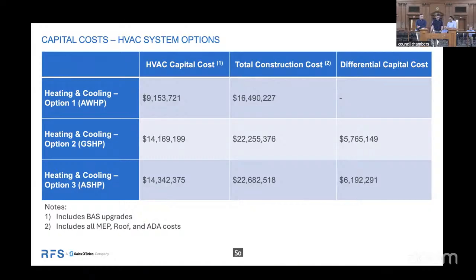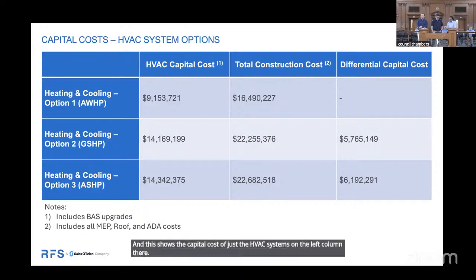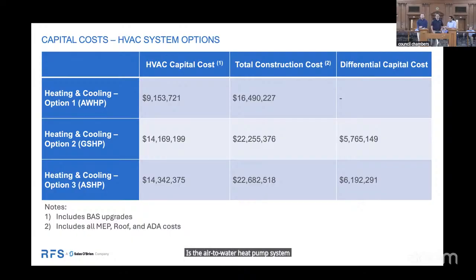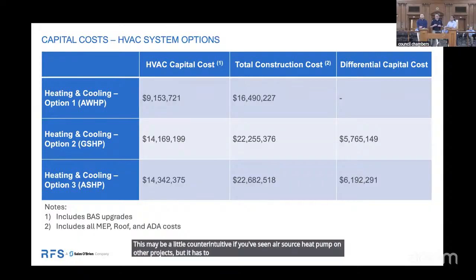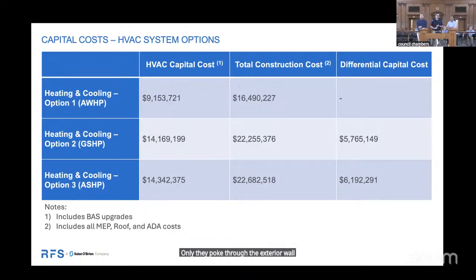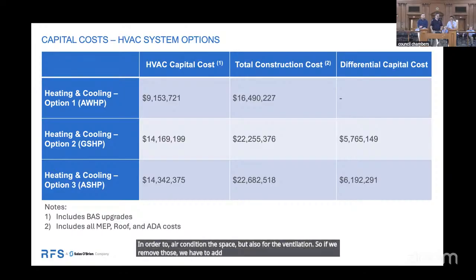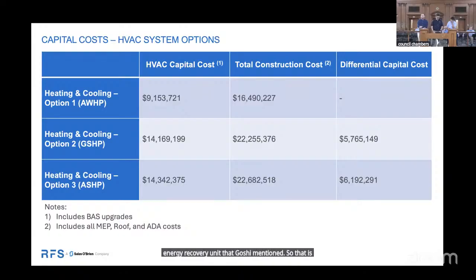This shows the capital cost of just the HVAC systems in the left column. You can see the cheapest capital cost is the air-to-water heat pump system. This may be a little counterintuitive if you've seen air source heat pump on other projects, but it has to do with the nuances of this project, specifically that we are removing the unit ventilators. The unit ventilators, as Goshi mentioned, not only poke through the exterior wall to air condition the space, but also provide ventilation. So if we remove those, we have to add back in ventilation, which is the dedicated outdoor energy recovery unit that Goshi mentioned. That is why the capital costs of option 3 are a bit higher.